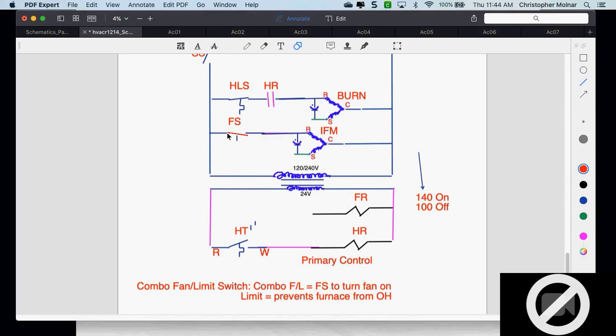Or my fan switch, I could put that right there. Okay, and as the temperature of the ductwork warms up, I could pull my limits up. I can turn my blower motor on. Okay, and that should be a thermostat looking switch up there, and it's just not going to cooperate for me right now. Okay, so I could put my fan switch there, and then I don't need this down there at all. It all of a sudden makes my diagram, my low voltage side, easier. That's one way it's wired.